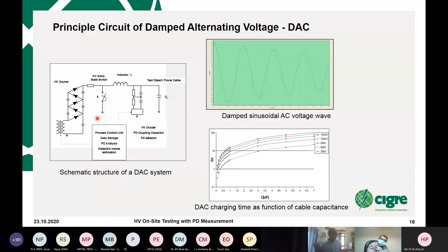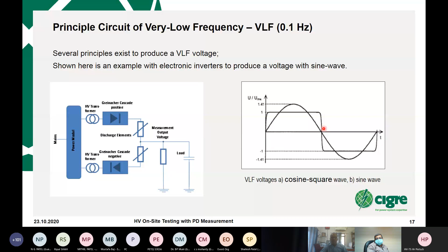The other possibility, which I mentioned briefly, is one I don't like to go into in terms of technology. This is one possibility. There are different ones, but more important is that there are two ways to produce 0.1 hertz. This is normally allowed in Europe and some other countries worldwide, and in the US even 0.01 hertz. The main stress is sinusoidal, but with very few polarity reversals, which are very important for the PD activity. The other one, which is also allowed, is the rectangular wave shape, like here. Again, you have the same number of polarity reversals, and the steepness is a bit higher. This also has an influence on the PD activity. This is very important.